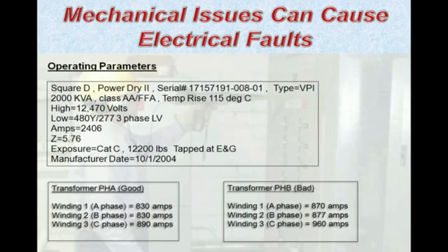Just to give you an idea of the type of unit we're dealing with here, this is a Square D manufactured transformer. It's 2000 kVA. It's air-cooled with a temperature rise rating of 115 degrees on the winding insulation. The high side is 12,470 volts. Low side is 480-277, three-phase. It's rated at full load for 2,400 amps and has an impedance of 5.76%.